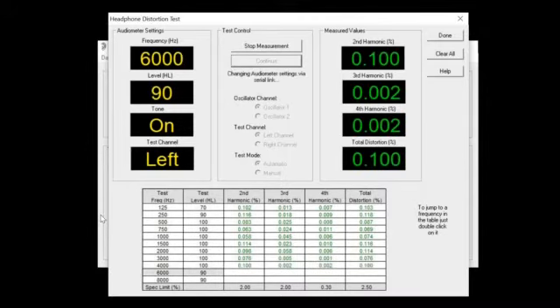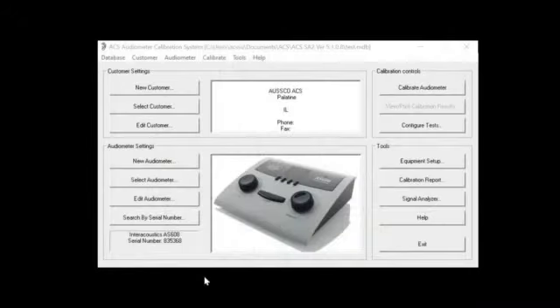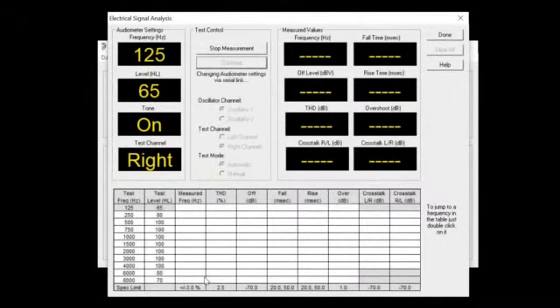As you can see over here, we've changed the output of that audiometer all the way from turning the intensity level from 70 dB up to 100 and back down into 90. That's the manufacturer's specification. And here we're on to the electrical analysis of it. We're talking about the frequency response, the total harmonic distortion, this off to on signal ratio, the fall time, the rise time, the overshoot, and I guess we've selected on here not to do the crosstalk at 125.